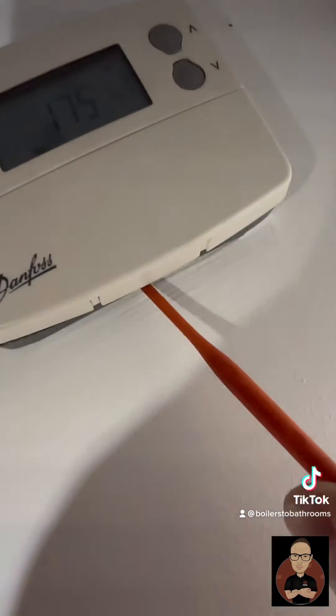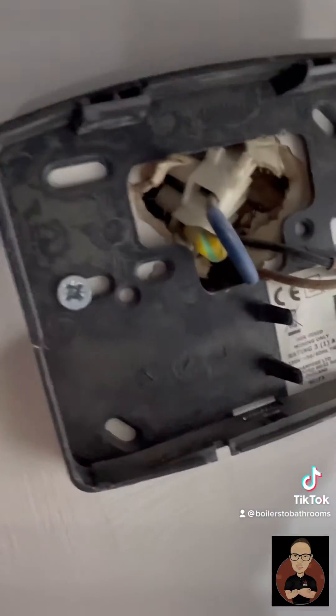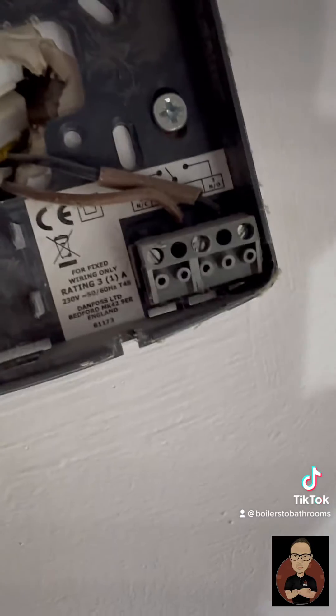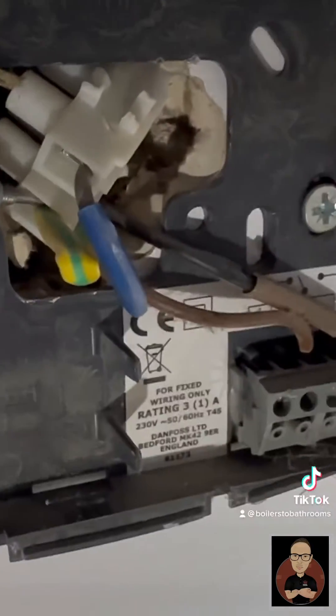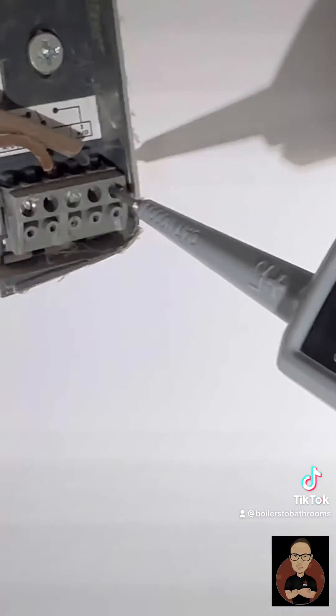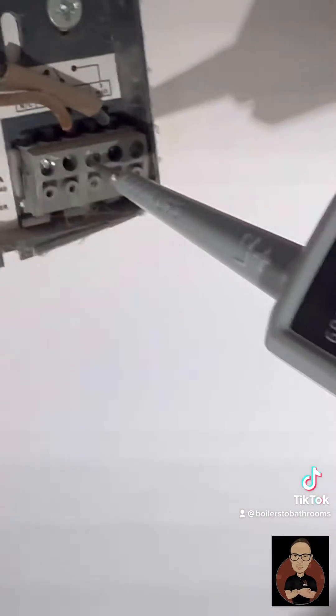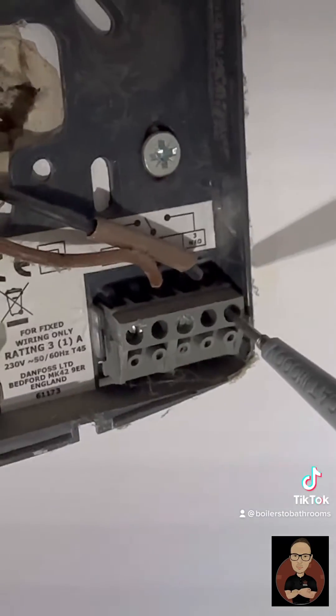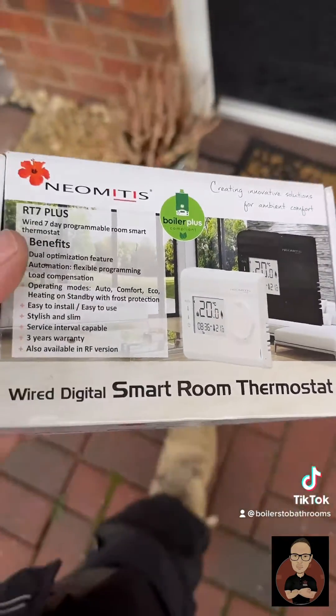Pop a flathead underneath just to pop the front off, and that'll whip off exposing two cables. You've got your common, which is your permanent live, and then you've got your normally open, which is your feed up to the zone valve. So when you're calling for heat it makes the connection and sends voltage up to the zone valve. We're getting 240 on common, which is your permanent, but nothing on the other one.